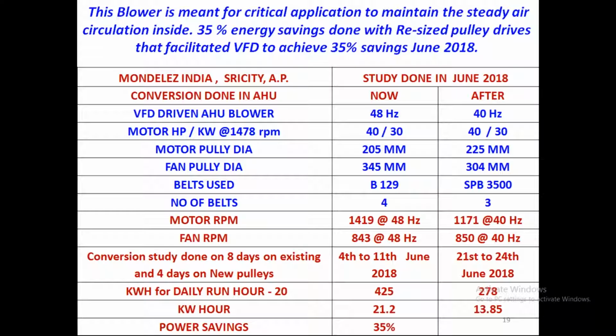It is purely by the resizing of the pulleys and the VFD; the flexibility of the VFD is put to use in this application, and straight away 35% savings is done. And it is a critical application. They have to maintain a temperature and RH at 22 degrees, especially as it's a chocolate factory where you cannot have any risk with the air changes. But having taken this study, they are running this for the past 3 years at 35% energy savings, and still the factory is running and the air circulation is achieved.